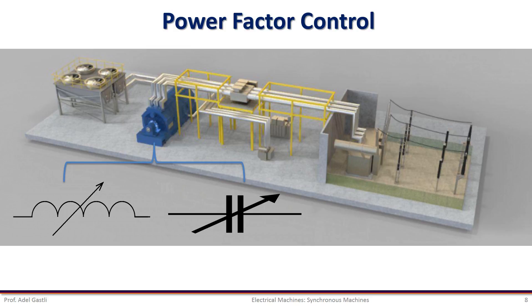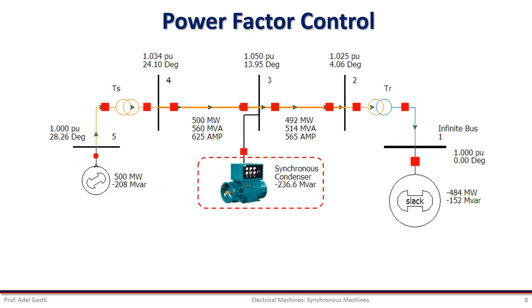Looking from the machine terminals, the machine behaves as a variable inductor or variable capacitor as the field current is changed. An unloaded synchronous machine is therefore called a synchronous condenser and may be used to regulate the receiving end voltage of a long power transmission line.